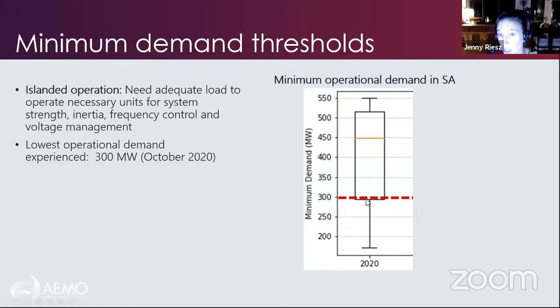So to address this, what we're doing is putting in place the ability to actively manage that rooftop PV. So we essentially need to be able to turn down those rooftop systems when necessary. We anticipate doing that very much as an emergency measure. So it would be something analogous to a load shedding mechanism, except in reverse, to be shedding PV. We're very conscious that we're shedding very small customer systems, but we believe we're at the point where it's really essential that we have that capability in place so that our control room can turn those systems down if necessary. So we've been working with the distribution providers to put that in place, and that is now underway in South Australia to implement that for all new PV going in. Even very, very small 5 kilowatt systems must now be installed with the ability to turn them down if necessary.